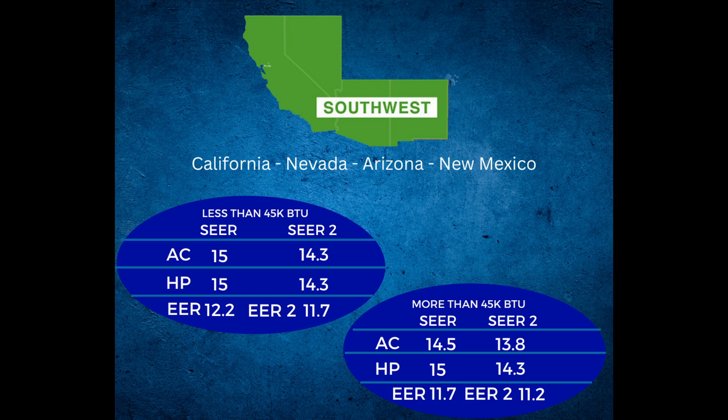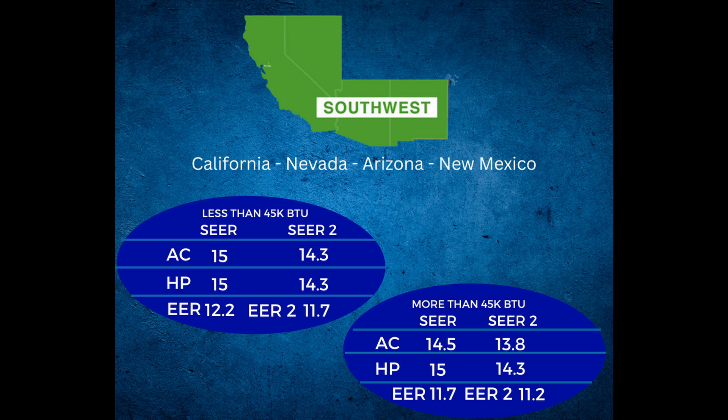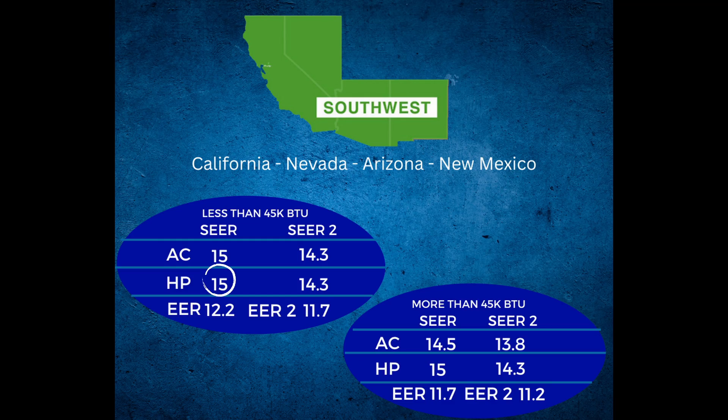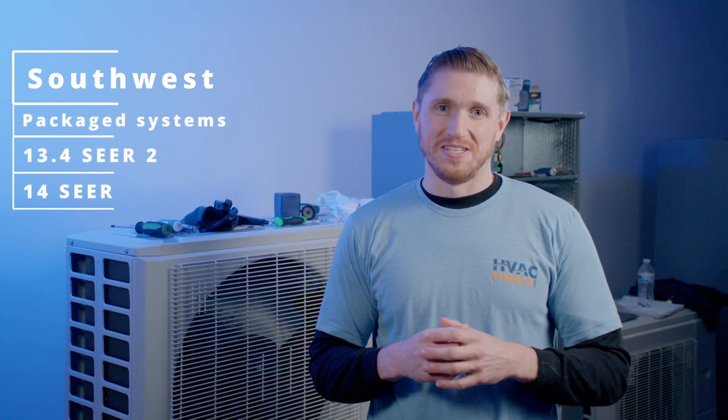That covers all you need to know for air conditioners in the southwest. Luckily, for heat pumps it gets a little simpler — all we're looking at is SEER or SEER 2. With heat pumps, we also do not need to look at the BTU requirements in the southwest region. For heat pumps, the SEER 2 minimum is 14.3 for all heat pumps manufactured January 1st or later. Old heat pumps made in 2022 that are 14 SEER do get grandfathered in. For equipment made on January 1st or later, the SEER rating bumps up to 15. So if your heat pump was made before 2023, it can be 14 SEER; if made on or after January 1st, it has to be 15 SEER or 14.3 SEER 2. And for all package systems, the rating is 13.4 SEER 2 or 14 SEER.